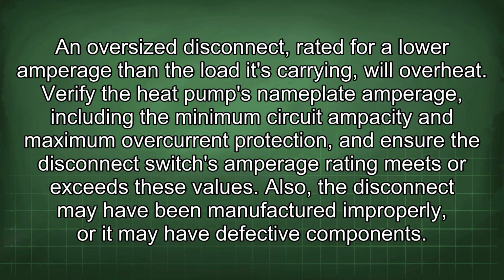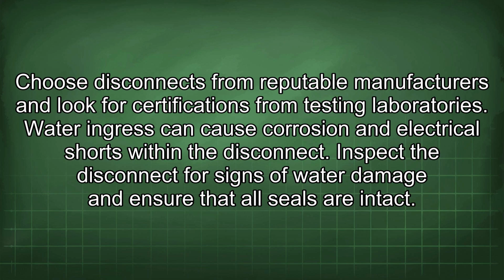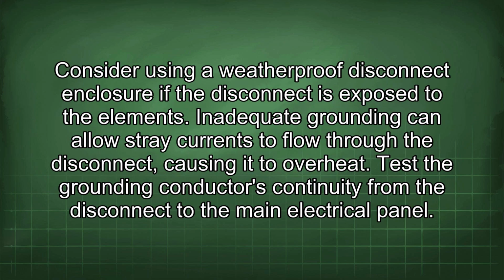Also, the disconnect may have been manufactured improperly, or it may have defective components. Choose disconnects from reputable manufacturers and look for certifications from testing laboratories. Water ingress can cause corrosion and electrical shorts within the disconnect. Inspect the disconnect for signs of water damage and ensure that all seals are intact. Consider using a weatherproof disconnect enclosure if the disconnect is exposed to the elements.